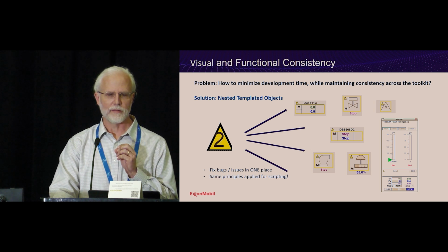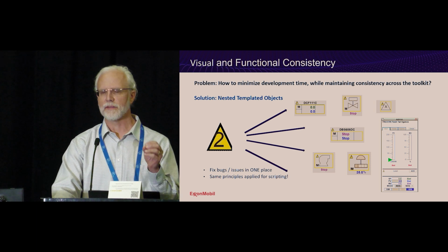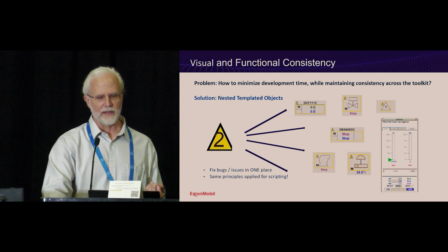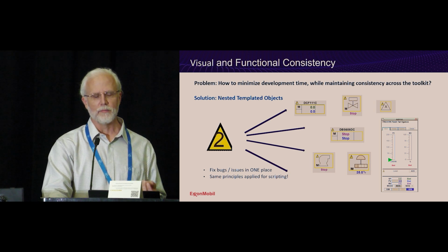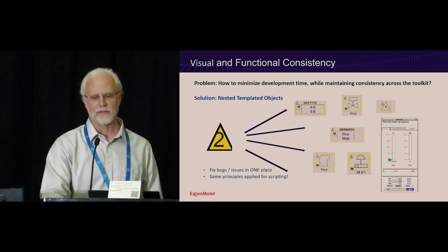And this philosophy of making use of embedded objects and using the same objects gives you this consistency. But not only that, if there are any changes that need to be made, you make it down in the lowest level object, and that change then propagates to all of the instances and uses of it anywhere on the HMIs without having to go through and update individual displays.